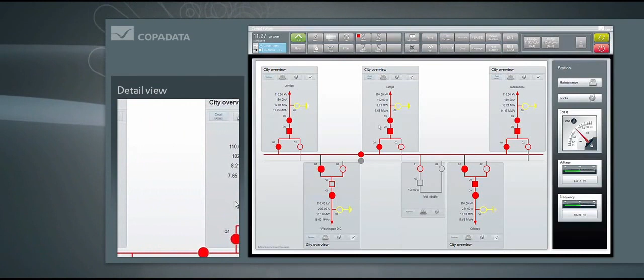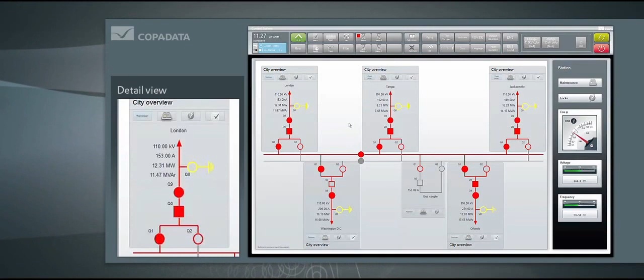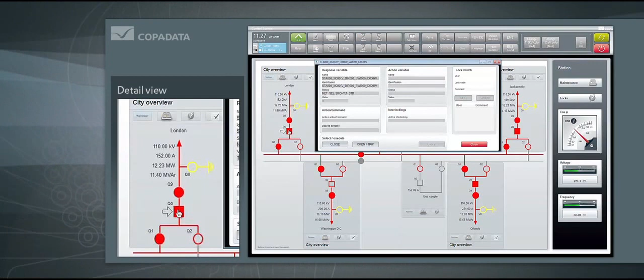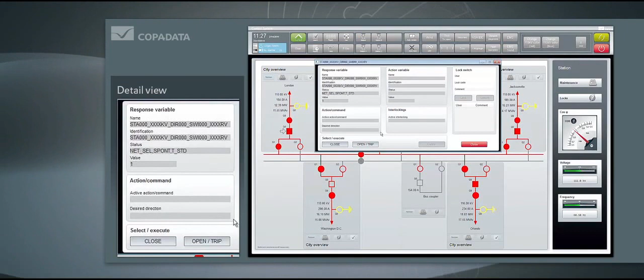We want now to unpower the feeder London. Therefore, we have to open the circuit breaker Q0. By clicking on the circuit breaker Q0, we see the so-called select arrow showing this tag as selected in the HMI network. With the command processing window, we are able to open the circuit breaker.